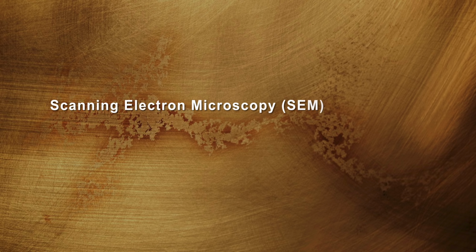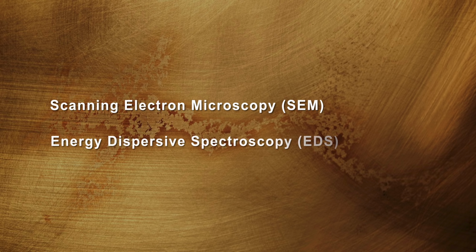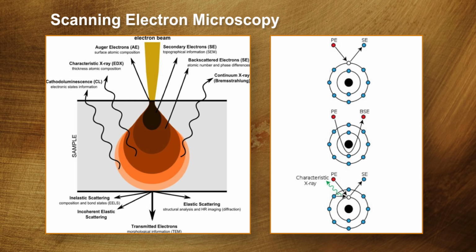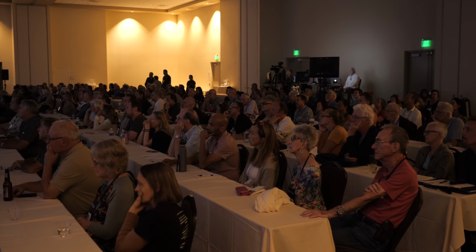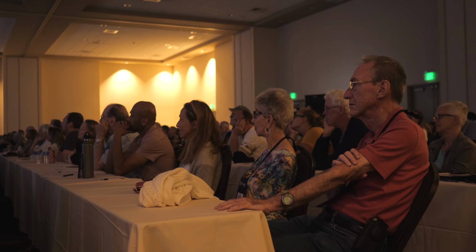So, scanning electron microscopy. There's also an additional technique on here: energy dispersive spectroscopy. And what I'll do is I'll show you a quick slide on where that energy dispersive spectroscopy comes in. I should have had a slide on the scanning electron microscope as well, but if you picture a regular optical microscope, you look through the top and it goes through a series of lenses. The light comes up from the bottom through your sample and you can see it. And really the way an SEM works is that you replace your eye with an electron source, an electron gun, that gets shot through a series of magnetic lenses, which then hits your sample, which is mounted, and again, this happens in a vacuum. And then a detector is off to the side to detect the electrons that bounce off your sample. So not only do you get a secondary electron image, if you will, an emitted image, but you also get other stuff coming off of that as well.